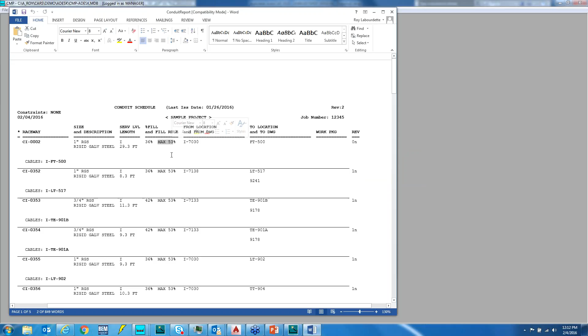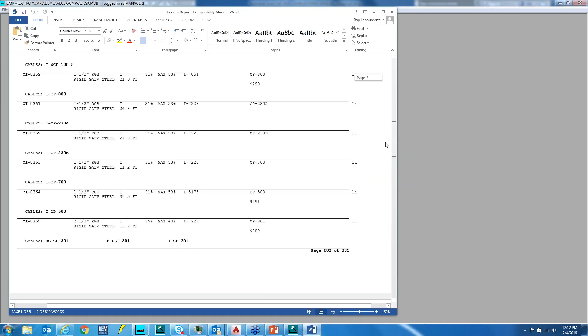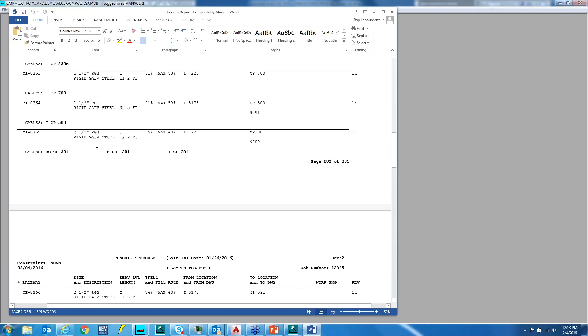So the first conduit here is C0002. It's 1-inch RGS. There's one cable in that conduit. It is 36% full with a code maximum of 53%. If I scroll down, I find this conduit actually has 3 cables in it, so its maximum by code is 40%. As you change the number of cables that you put in a conduit, it changes the fill percentage that's allowed by code. So this 2.5-inch conduit is 35% full, so it meets the code requirement, and the program is using the minimum size conduit that meets that code.